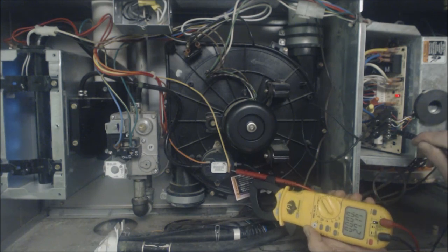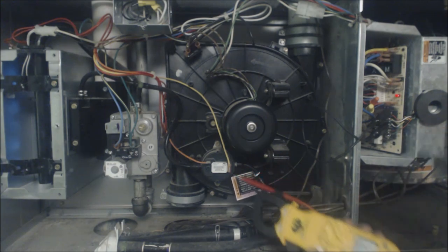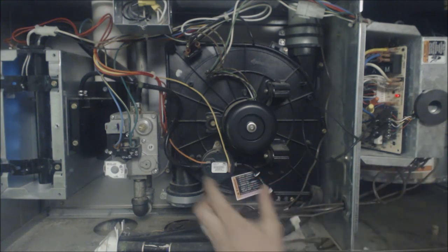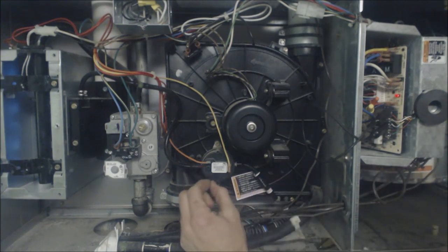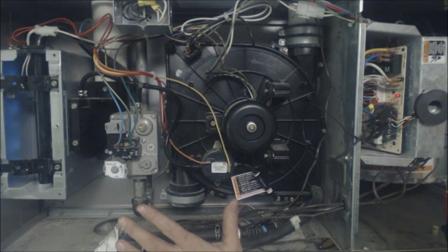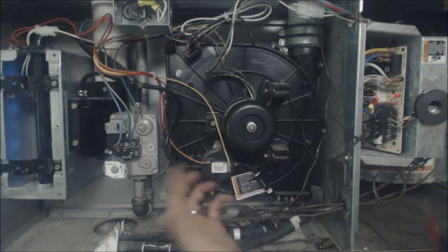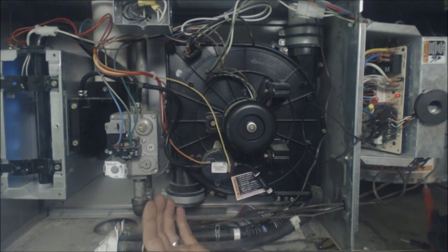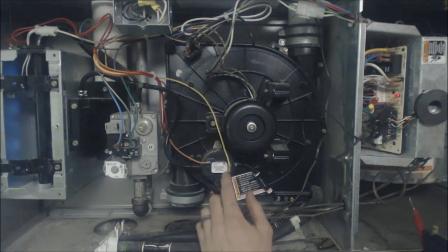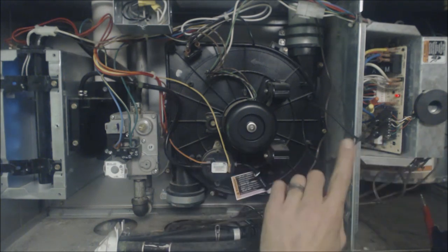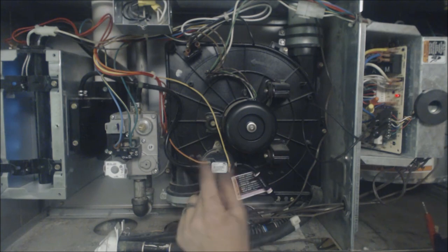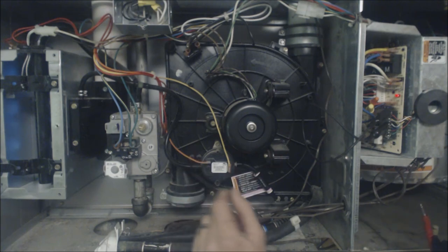We're going to do the same thing on the terminal and the common, we got 27 volts together. So that tells us that this pressure switch is closed and that everything is working properly. But if we did not have 24 to 28 and a half volts from here to common or from here to common, then that means that this pressure switch is not electrically closing.